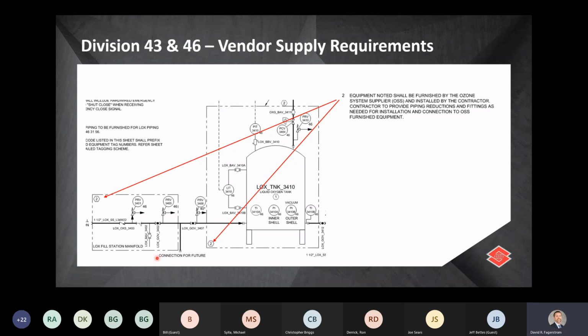As you typically see on jobs, our drawings identify with dash boxes the limits of supply for various components. Pay attention to that, so when the P&ID shows these valves or instrumentation devices are within this box and, in this case, expected to be furnished by the ozone system supplier, those are included in your scope. We've tried to cross-reference those to give an accurate, clear representation of what is required, but we ask that you also pay attention to those details as well.